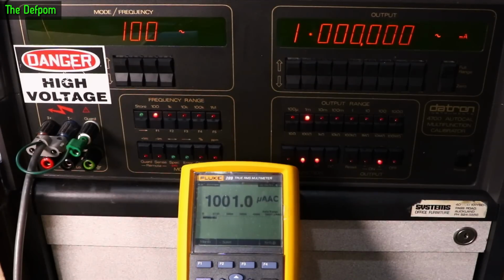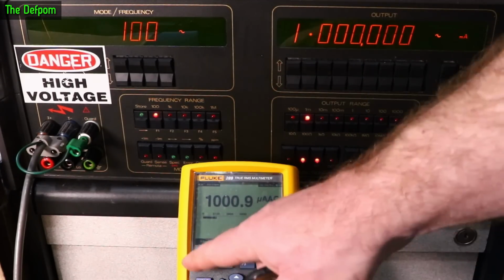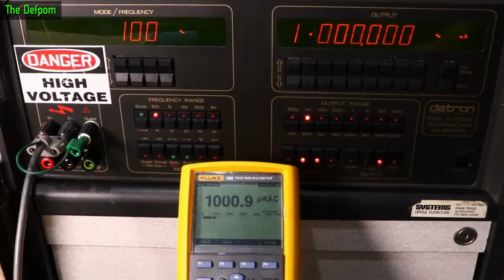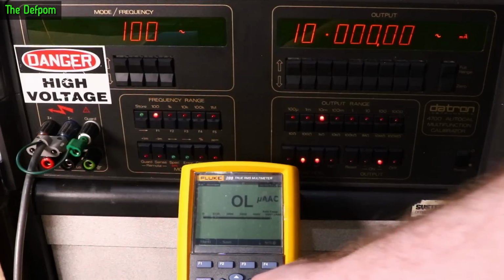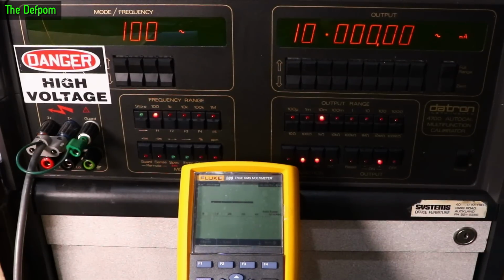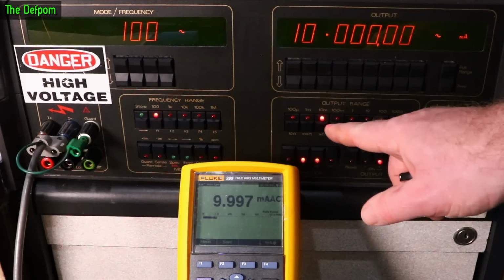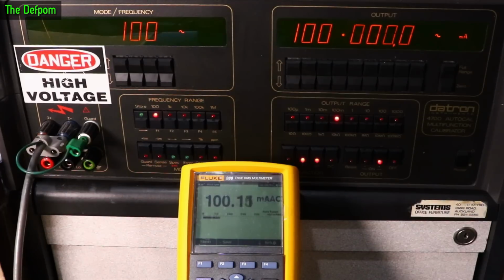So I've changed over to AC amps now. So I'm on my milliamps range. 1 milliamp I'm doing here. I've changed the meter over using the menu button here. And you can see we're about 9 counts up at 1 milliamp at 100 Hertz. 10 milliamps is out of scale on the microamp range. Milliamp range. So 10 milliamps is a couple of counts down there. So maybe 3 counts, let's say. 100 milliamps, you're just looking at about 4 or 5 counts up.